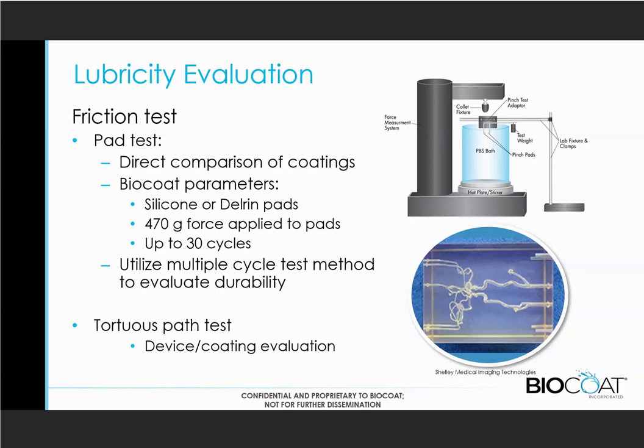The primary one we do is what we call a vertical pinch test or a pad test, where we take two pads and plates that we squeeze together. For us, we're using 470 grams of force with either a silicone rubber or, in more aggressive cases, a Delrin pad. We squeeze that together and then pull the sample up between those pads, measuring the force that it takes to slide up there. We'll typically do up to 30 cycles, and actually can go up and down through there, measuring that force.